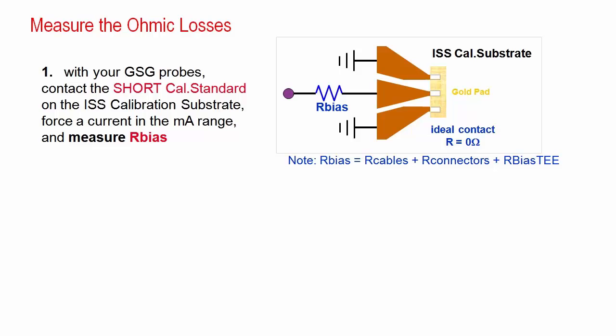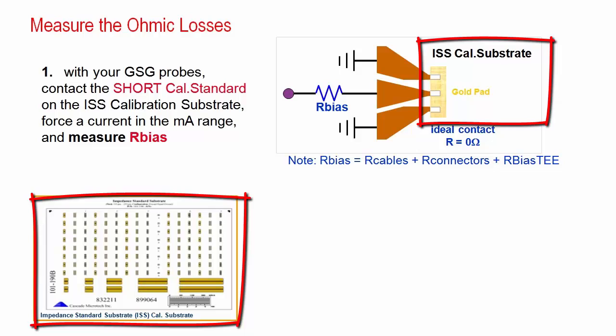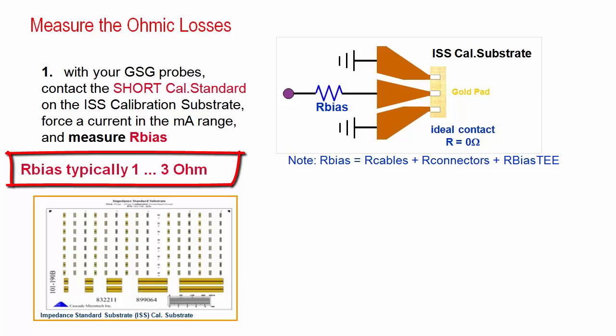I suggest to apply two steps. The first step covers the cable losses, the connectors and the bias tee. I connect the GSG probe to the golden contacts of the short on the ISS CAL substrate. This short will be applied later for the calibration of the network analyzer. Its gold contacts are considered as ideal and we measure the sum of all the other losses. The measured value is usually between 1 to 3 ohm.